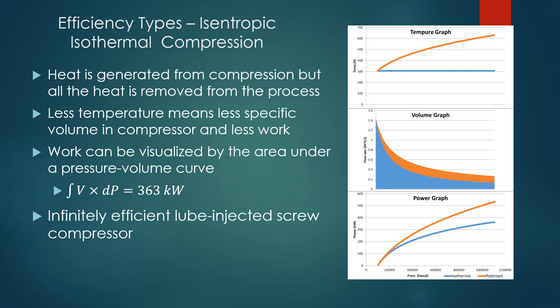The other type of theoretical compressor model is isentropic isothermal compression. In this form of compression, all heat generated by heat of compression is rejected to a heat exchanger. This allows the temperature of the compressed air to remain constant while the pressure increases. Less heat in the compressed air means less specific volume, and less specific volume means the compressor can compress air with less required work. The area under the volume-pressure graph represents the amount of work required. Because heat rejection is included in this model, it more closely resembles a lube-injected screw compressor. An actual lube-injected screw compressor would not be able to completely reject all heat generated, so it would fall somewhere between the two theoretical models.